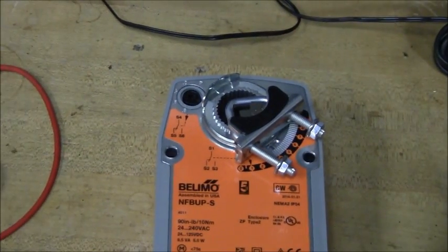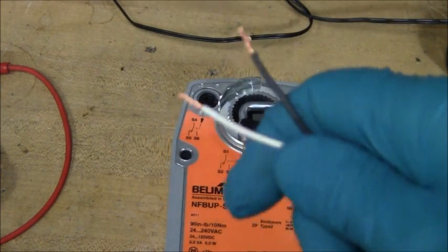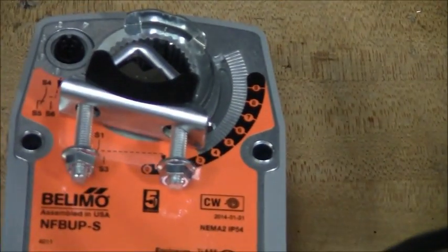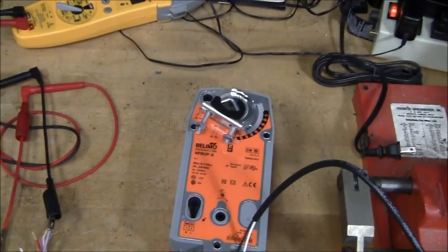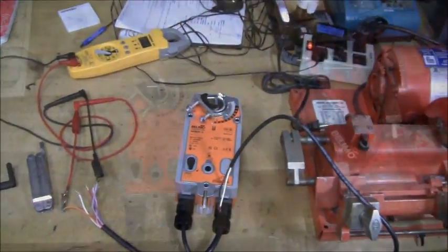I'll leave the meter on just for a second. I'm going to let this go to 100% on the cam. This is how this motor normally sits. I'm going to pull this out, so the electricity is now removed. And now you're going to see when that stops. Right there, you see that? Right about 50%, which is exactly what I've got it set for. So that's just to give you a quick tabletop demonstration.